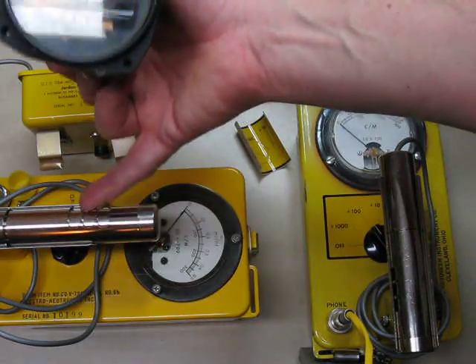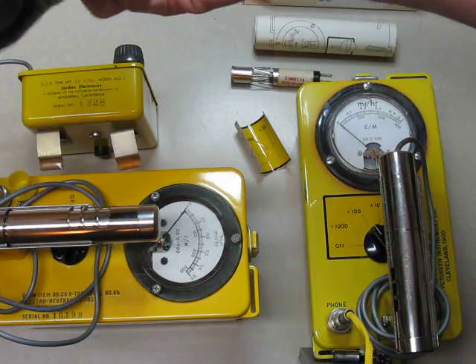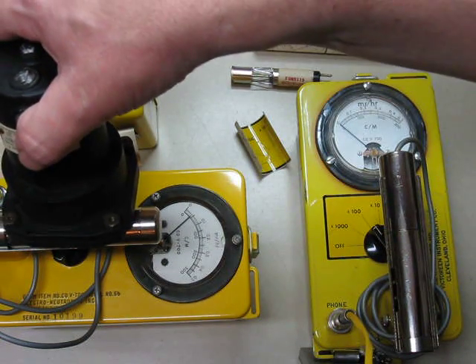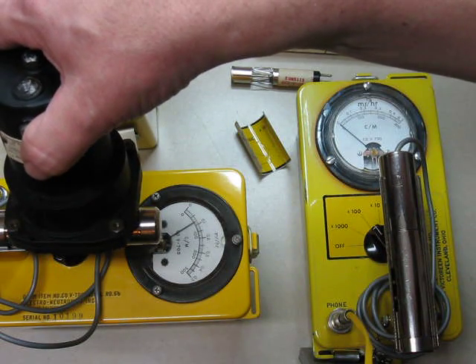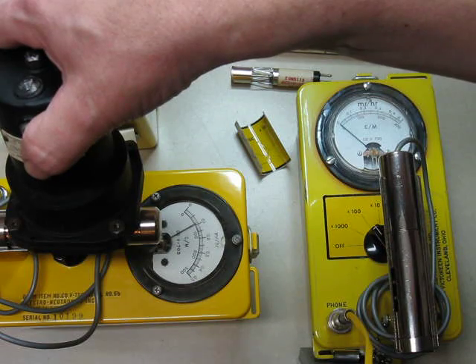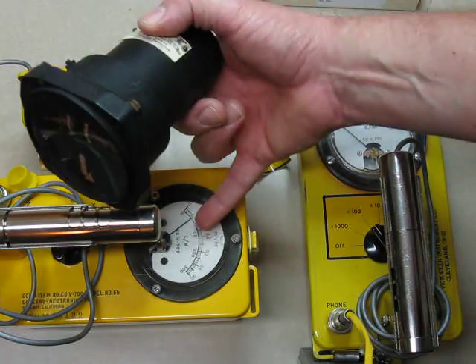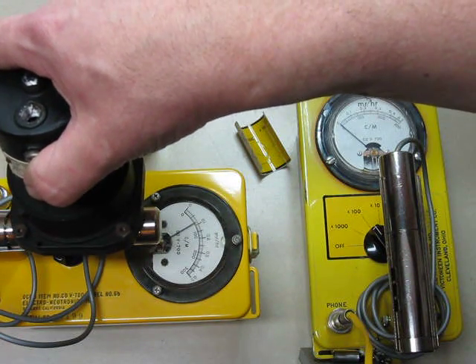I'm using my turn and bank indicator again - my aircraft turn and bank indicator. I'll put this on the unconverted CDV-700 with the standard tube in it, and you can see it'll read about 10 mR an hour. It's set right on top of the probe. It's on the x100 range right now, and it's coming up to .1, which is 10 MR an hour. It'll settle in about there.